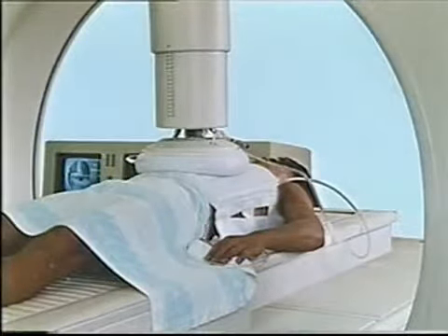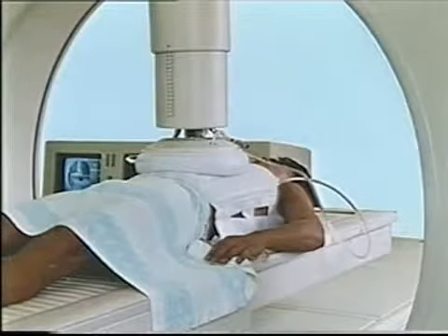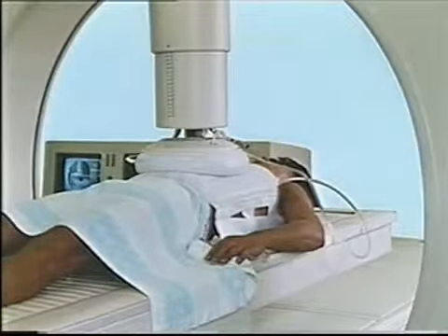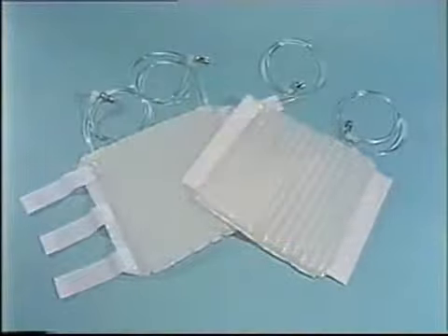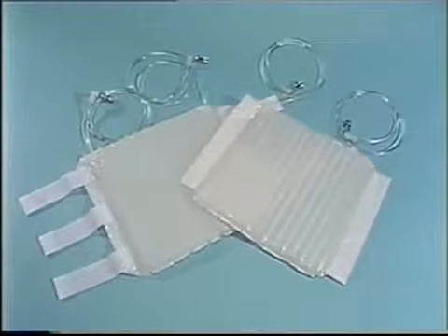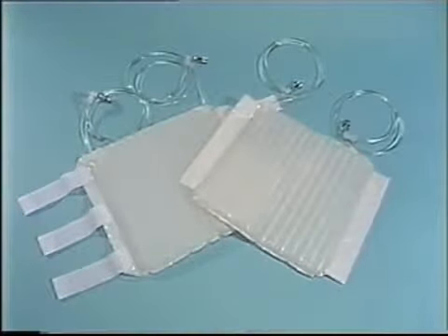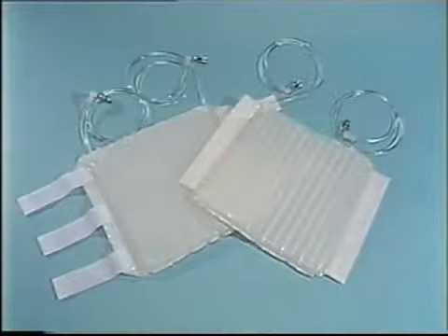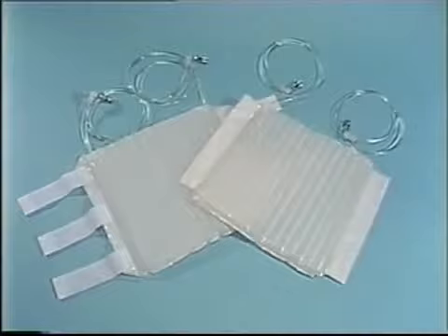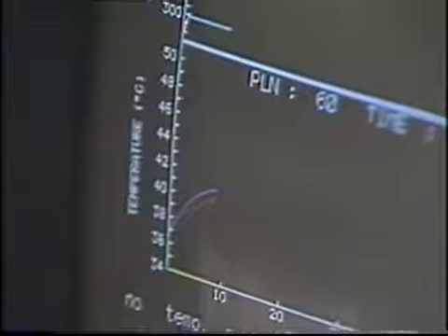Furthermore, by the use of pre-cooling, it has been found that excessive heating can easily be prevented, even of a fat layer about 25 millimeters thick. Thus, excessive heating of the subcutaneous fat layer, burns at the edge of the electrode, and a hot feeling and dull pain, which are the disadvantages of an apparatus of the capacitance type, are virtually eliminated.